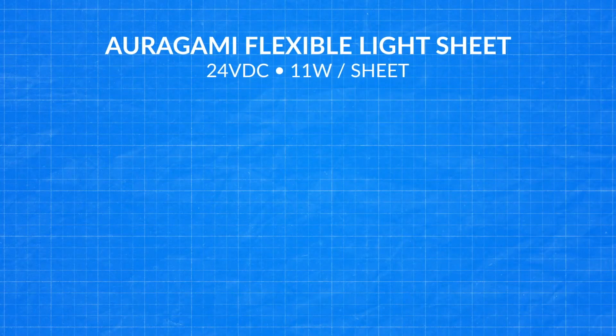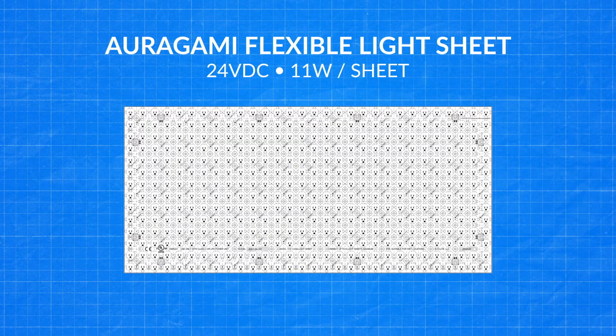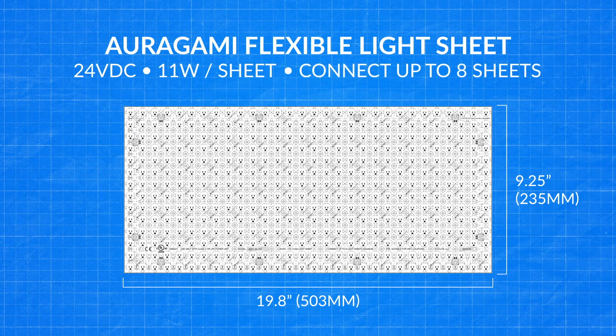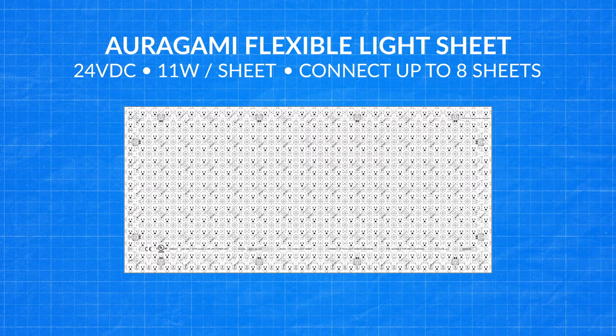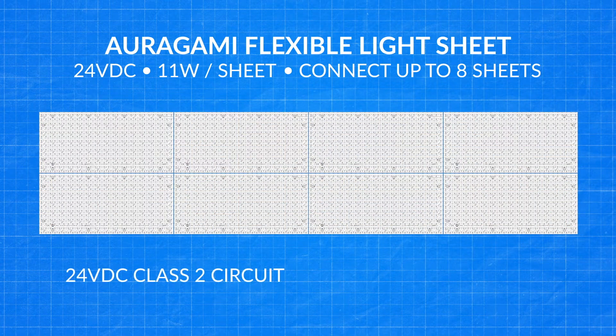Each 24-volt DC Auragami sheet uses 11 watts and is sized at 19.8 inches by 9.25 inches. You may connect a maximum of 8 full light sheets, which will result in 88 total connected watts. Auragami is designed to maximize a 24-volt Class II circuit while leaving the recommended amount of driver headroom to help maintain power supply longevity.